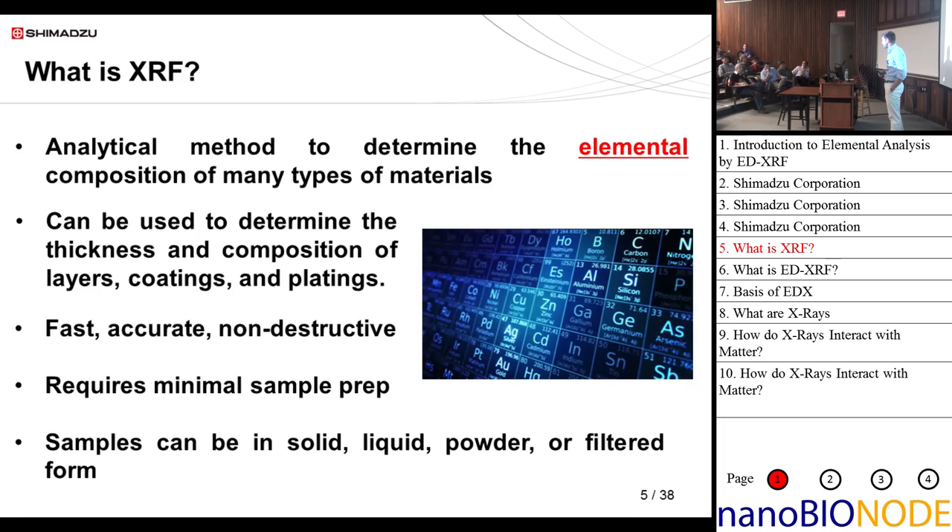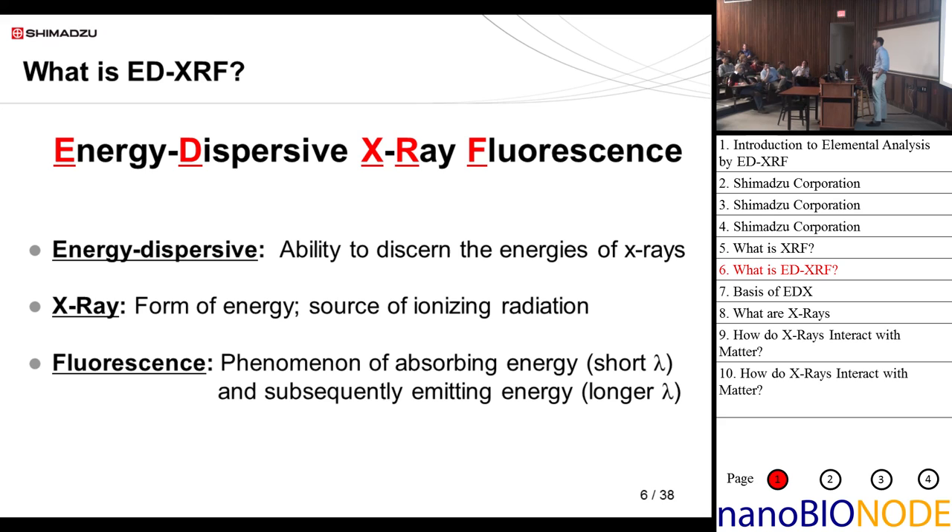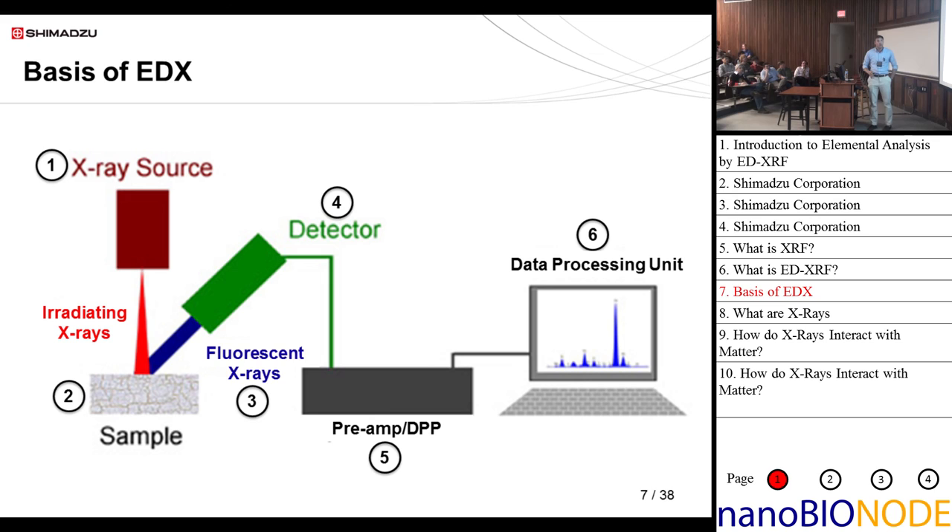So what is EDX? EDXRF stands for energy dispersive x-ray fluorescence. 'Energy dispersive' means we can discern the energies of x-rays. X-rays are a form of energy — in this case ionizing radiation. Fluorescence is the phenomenon of absorbing energy and then subsequently releasing energy. This is a basic diagram of an EDX: we have an x-ray source, a sample, irradiating x-rays that hit the sample generating fluorescent x-rays which are detected, then processed through a preamp and digital pulse processor, and on our PC we see the spectrum and get the quantitation results.